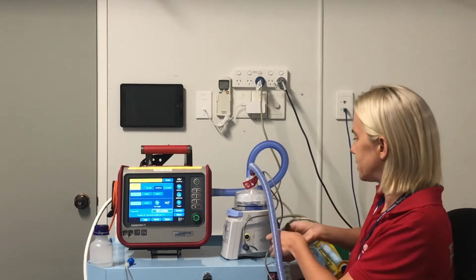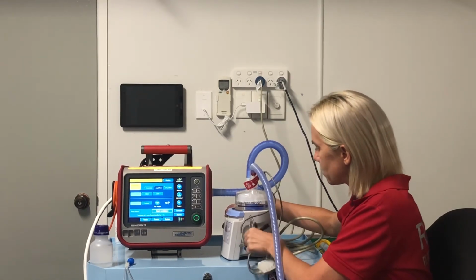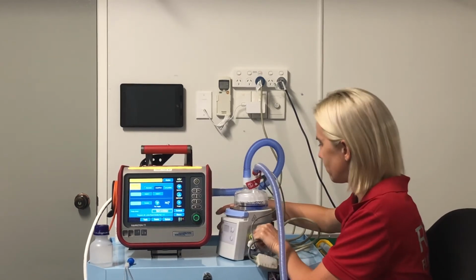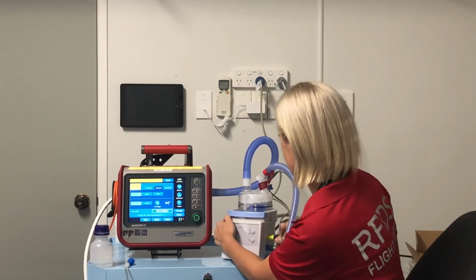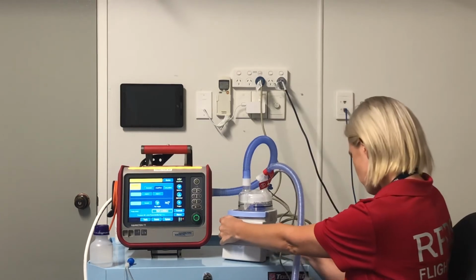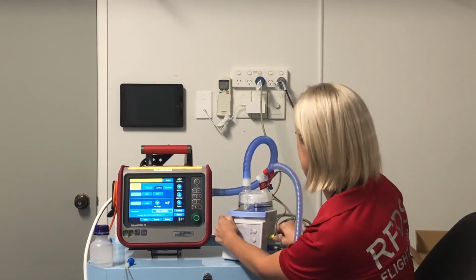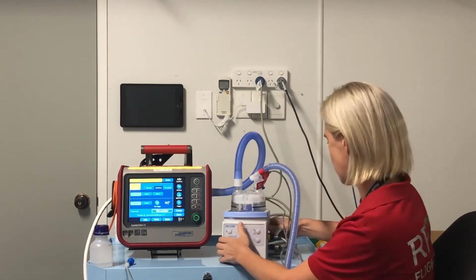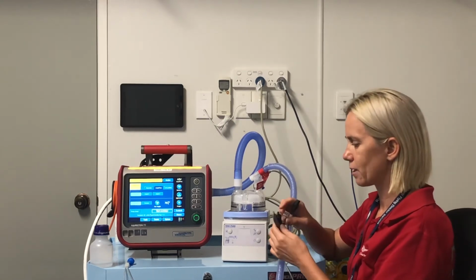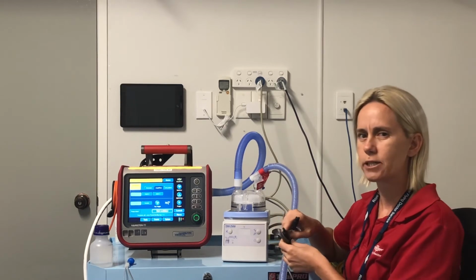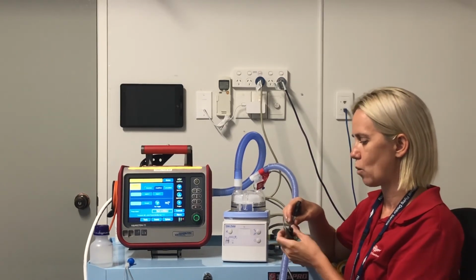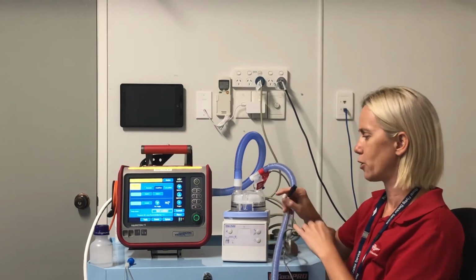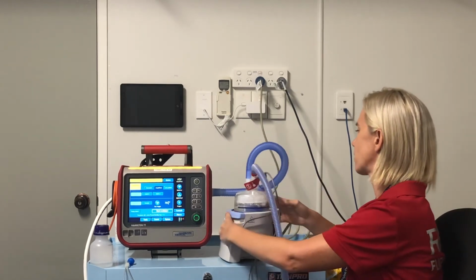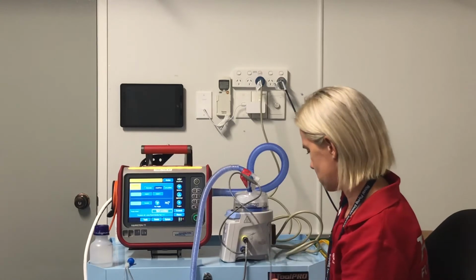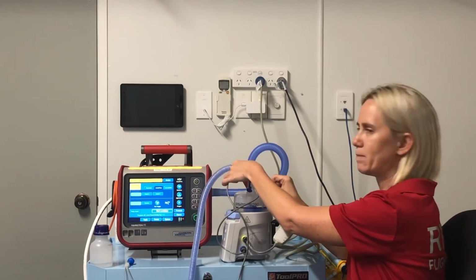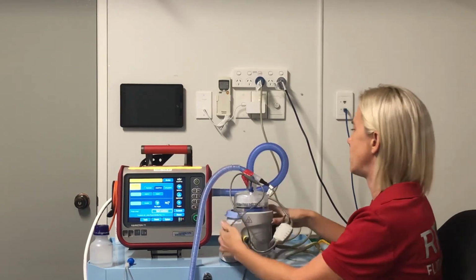So same again, just to the side of the humidifier, yellow to yellow. If I can get it in. Doesn't want to go. There we go. That's gone in now. And then with this one, it's also got a 2-prong and a 3-prong. It does say in the policy, and it actually comes up an error if you use the wrong one. I found it's easy to tag the one that you don't use, and this one is cabled up. So you use the 3-prong one, and that just connects into the back of the humidifier, where it keeps that temperature. So that connects in there to the humidifier.